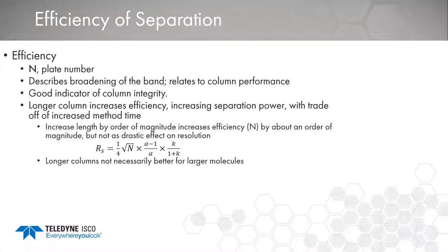The last component is the efficiency of the separation, driven by the plate count N of your column. This describes the broadening of the band as it elutes down the column and relates to your column performance. It's a really good indicator of column integrity. If your column is robust and performing well run after run with the same plate number, your chromatography performance isn't changing. If the plate count starts to decrease, that's usually indicative of some type of damage or degrading chromatography performance.